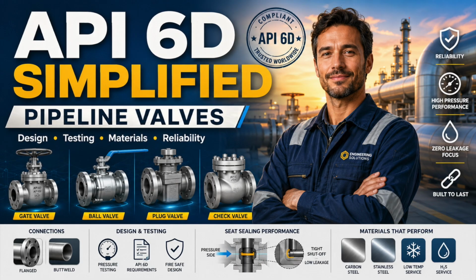You need maximum operating pressure, maximum design pressure, normal operating temperature, maximum design temperature, minimum operating temperature, minimum design metal temperature, startup conditions, shutdown conditions, emergency depressurization, hydraulic surge, gas expansion, potential Joule-Thomson cooling, trapped cavity pressure. The right question is not, can this valve hold the pressure? The right question is, can this complete assembly contain pressure and perform its intended function through every credible operating condition? That shift changes everything.